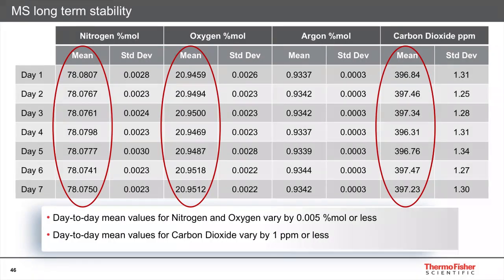The analytical performance of this mass spectrometer is shown by seven days of continuous monitoring of air gases. Mean values for nitrogen, oxygen, and CO2 are very stable over time. Typically, day-to-day mean values for carbon dioxide vary by as little as one part per million, and for nitrogen and oxygen in the region of 50 parts per million. This allows observation of very small changes in sparge gas concentration and composition compared to off-gas, yielding very precise measurements of respiratory quotients.